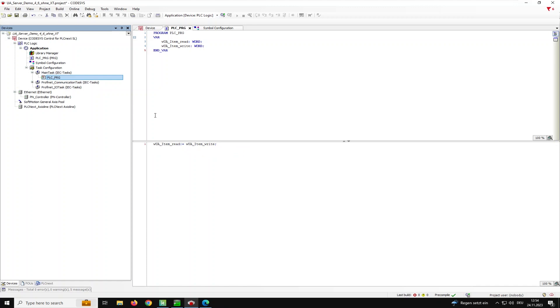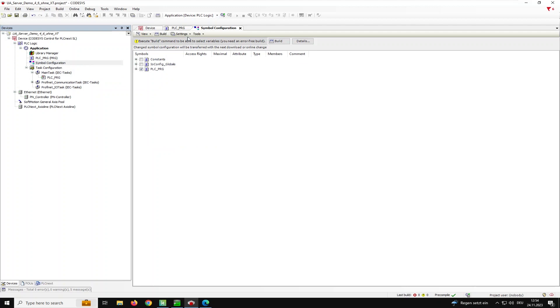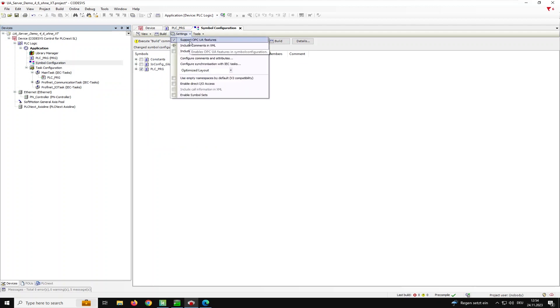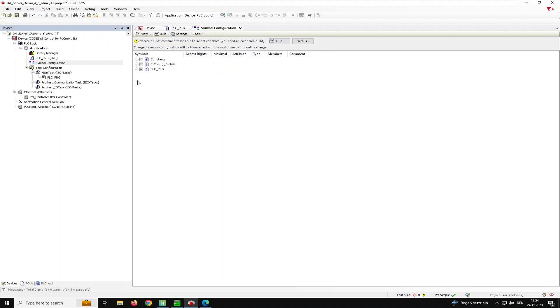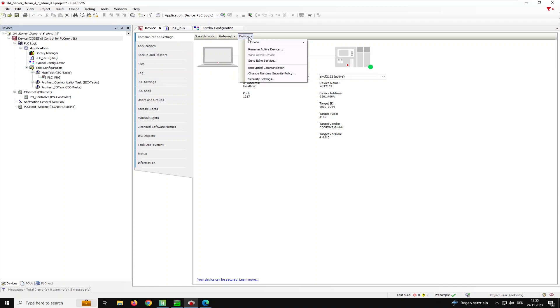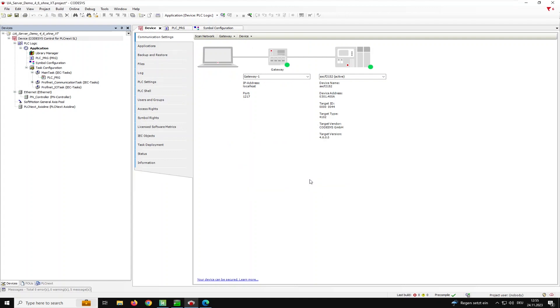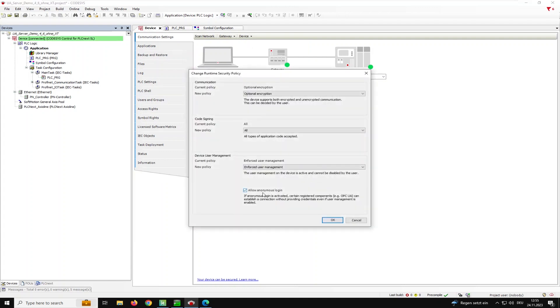To publish those variables to the OPC UA server, I added the symbol configuration. Activate under settings the OPC UA feature support and mark the used variables — in this case, both variables. On the device, I modified the security policy and also an anonymous login is possible.